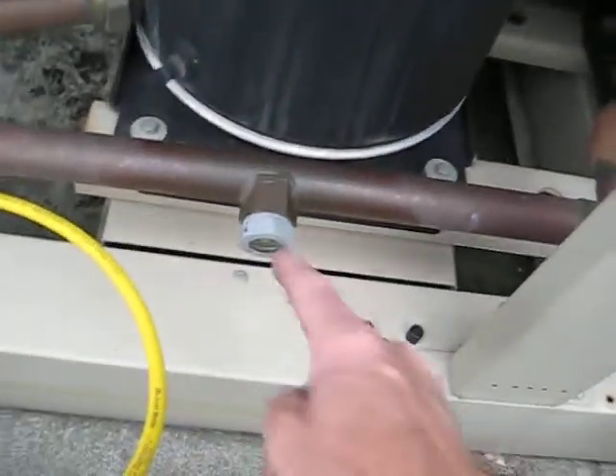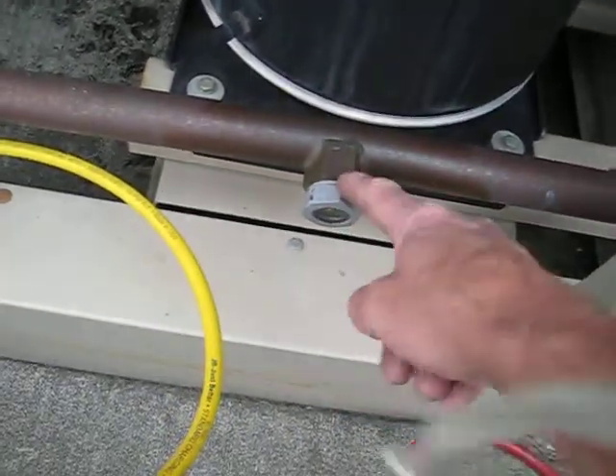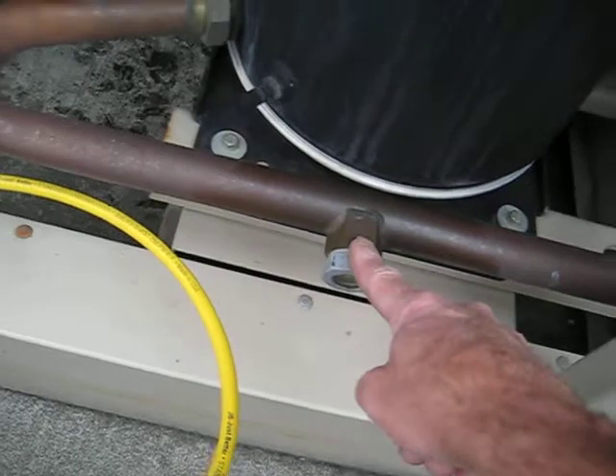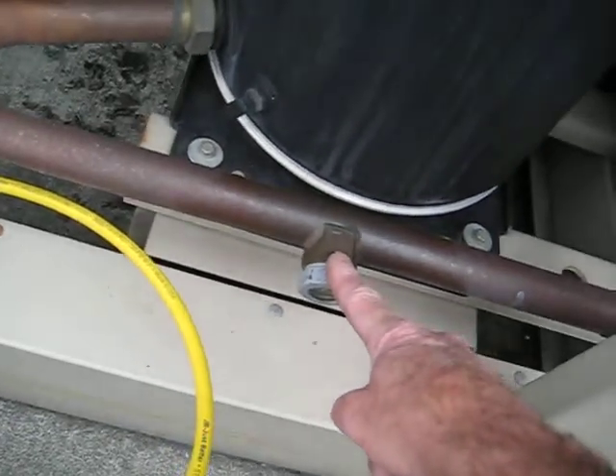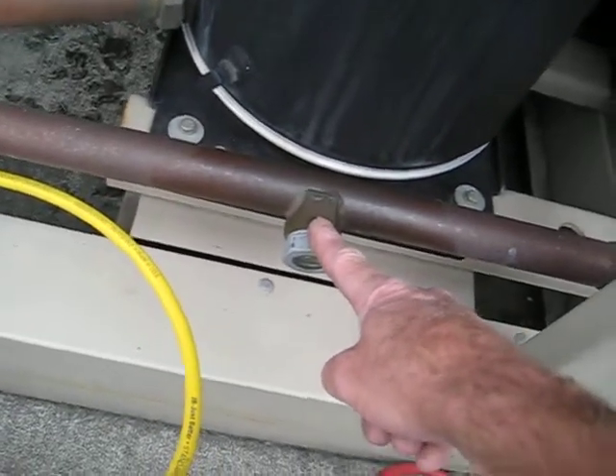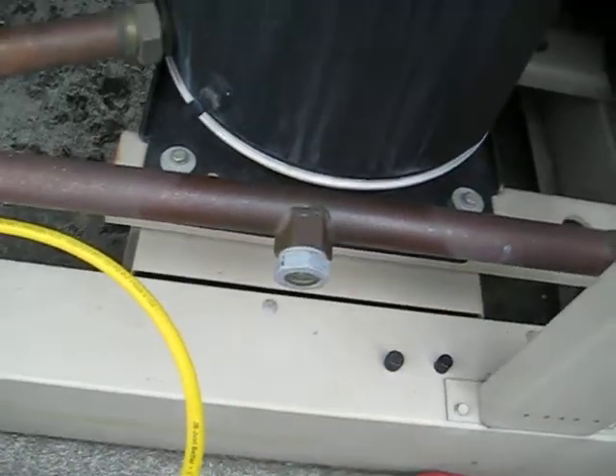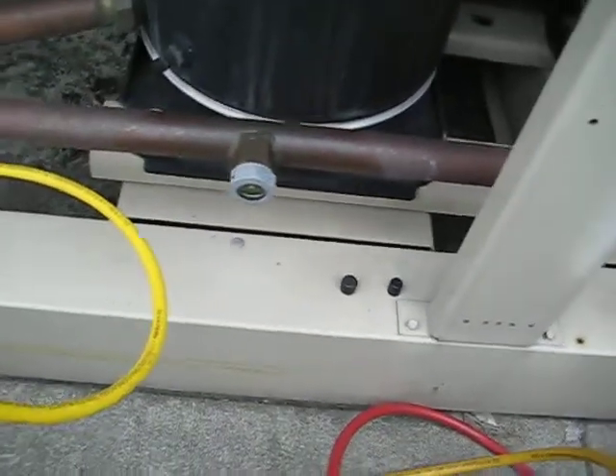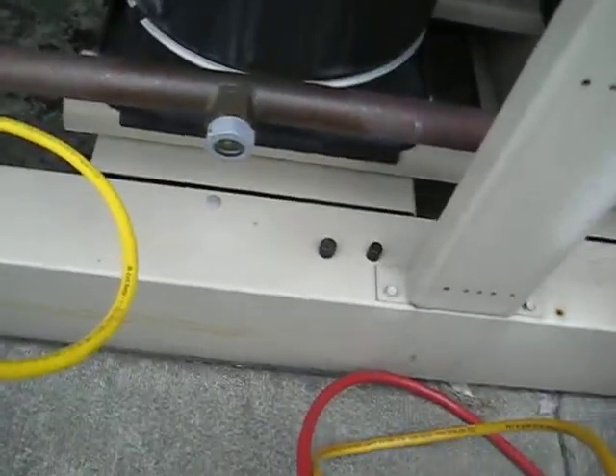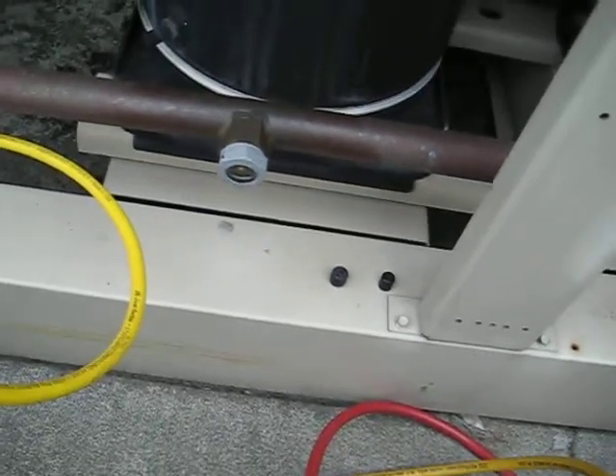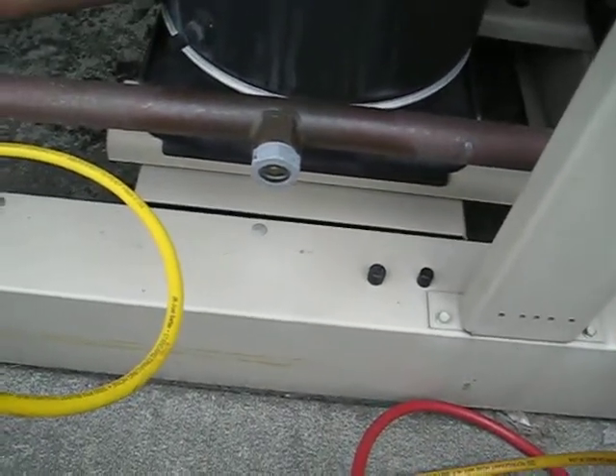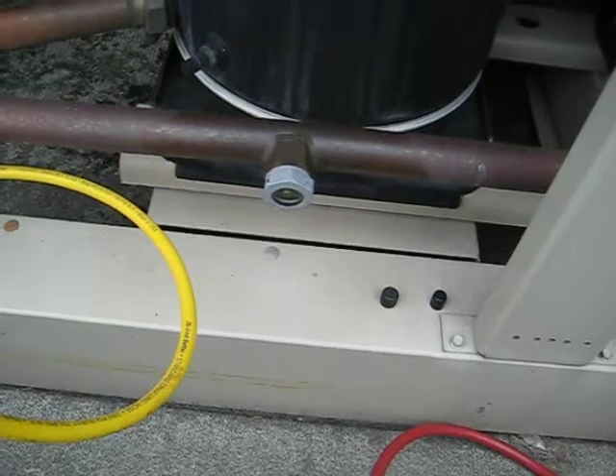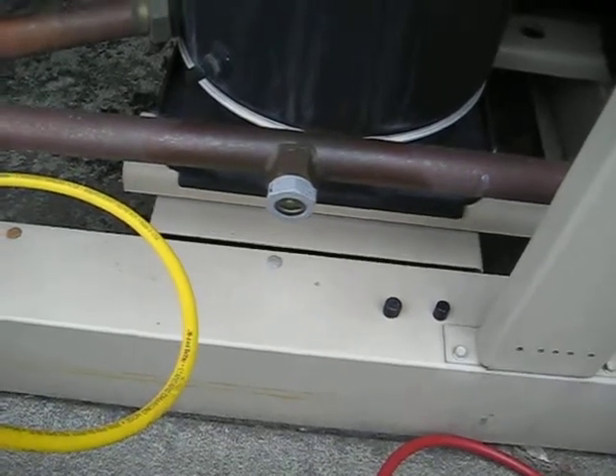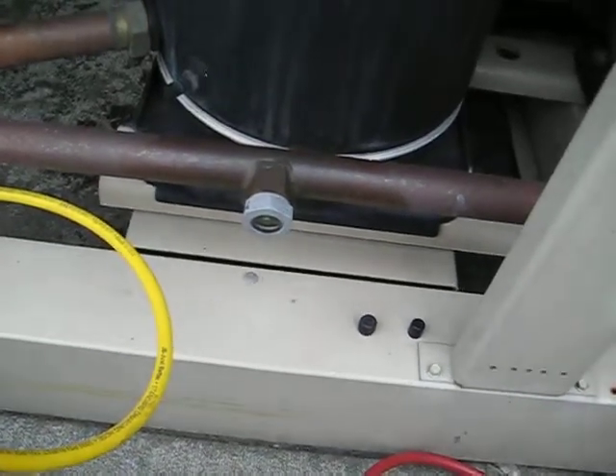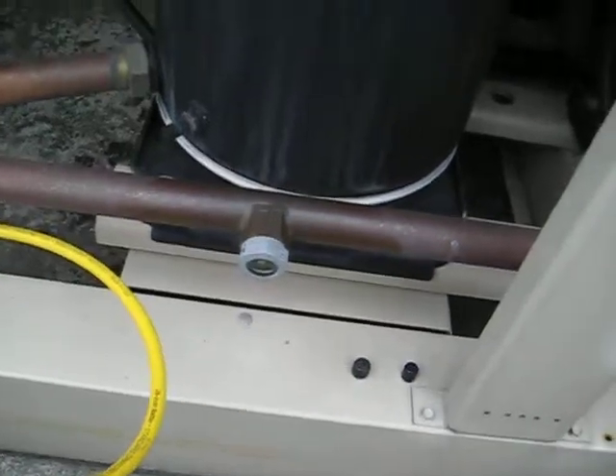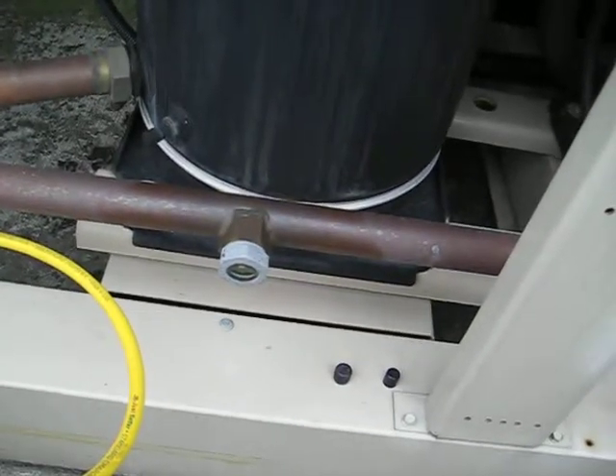My co-worker thinks that's one of the sight glasses right there. That's for lube oil between the two compressors. There's another one though. Each one has one other sight glass. He says those ones were leaking, so I have 2 brand new of those. Another co-worker said it's not going to leak through the glass, so we'd probably just use the old ones, because he seems to think that's pipe thread. I just glanced at them. I didn't think they were pipe thread, because sometimes they have weird threads on stuff, but maybe it is pipe thread. So I'm just going to use some really good sealant.